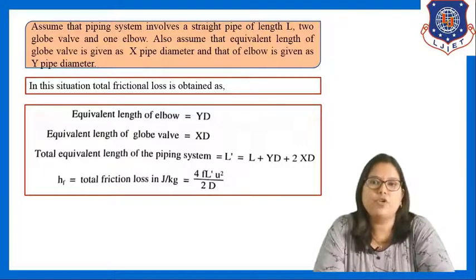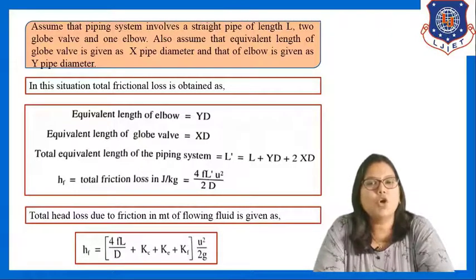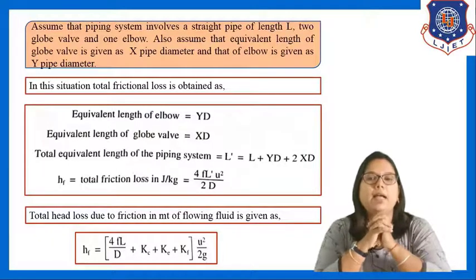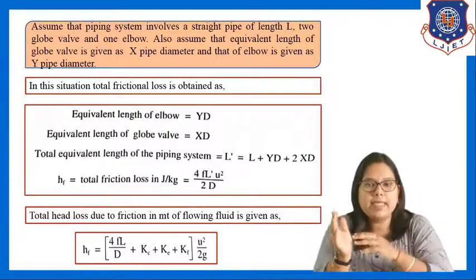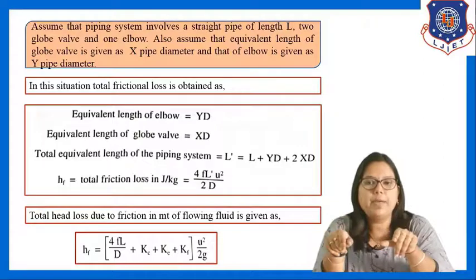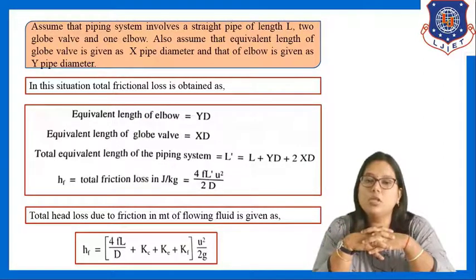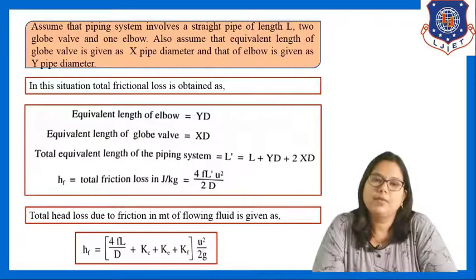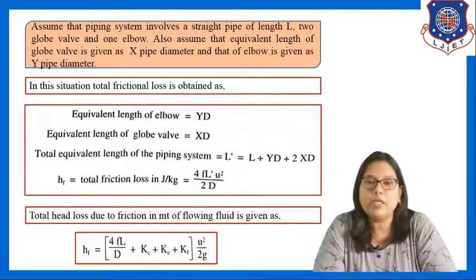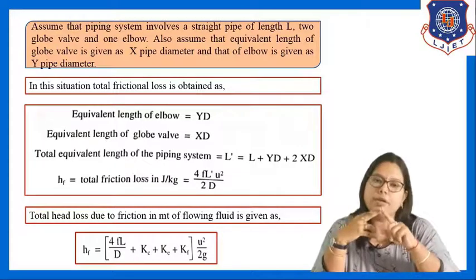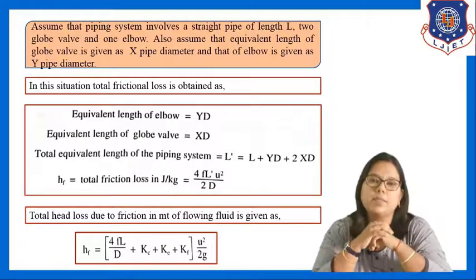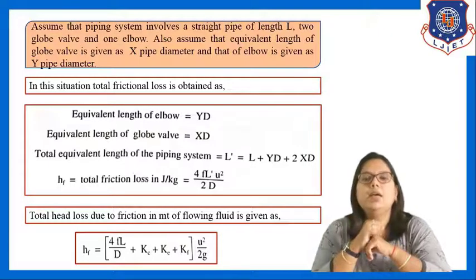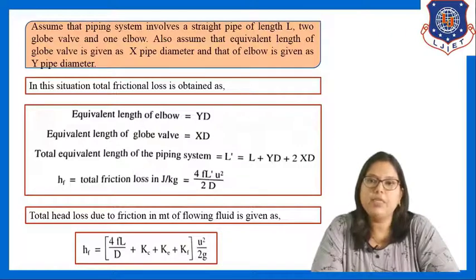Total friction loss is 4f·L'·u²/2d. The total friction loss in meters of flowing fluid is: Hf = [4fL/d + Kc + Kf + Ke] · u²/2g, where g is included because the loss is expressed in terms of head (meters of flowing fluid). This is the total friction loss for a system including straight pipe, sudden contraction, sudden expansion, and pipe with fittings and valves, written in terms of equivalent length.